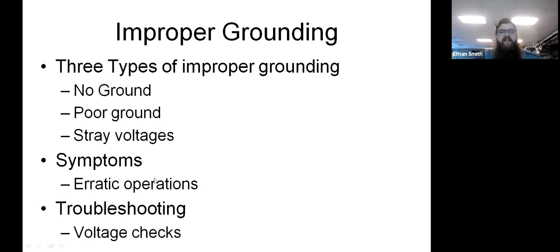And troubleshooting, guys, is you've got to go back to your voltage checks. In a 120 volt system, that's really easy. You go to that ground, you check voltage between line and ground, and you should have your typical line voltage. That should match your voltage between line and neutral, and your voltage from neutral to ground in a 120 volt circuit should be less than 3 volts. If you have more than 3 volts, you've got a grounding problem. Most of the times you guys will go out there, it'll be next to nothing between neutral and ground, but your upper limit's going to be 3 volts in a residential situation.